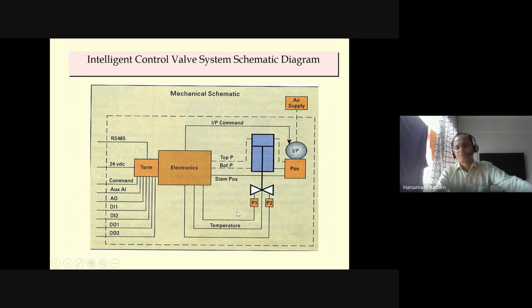in this valve you can have a measurement. You can see upstream pressure, downstream pressure, P1 and P2. Those signals, the sensors, are there. Then one more sensor is for temperature at the disk, plug and disk position, meaning actually where your seat and plug are. So there you have temperature sensors. So three important sensors monitor parameters. Through that, diagnostics are programmed. An algorithm is developed based on these inputs.